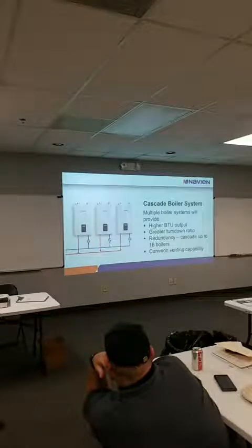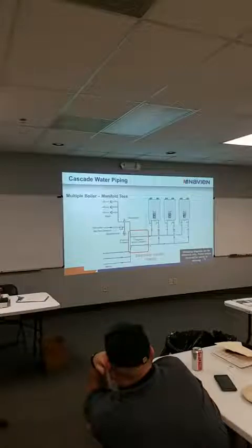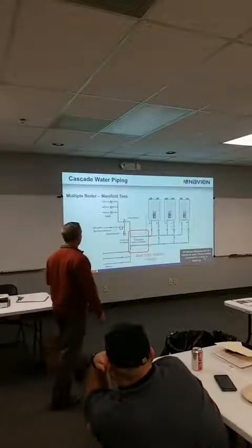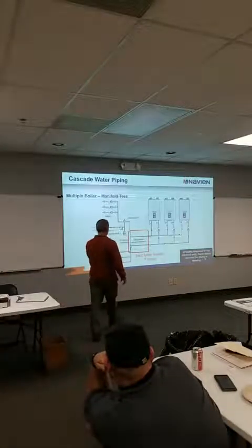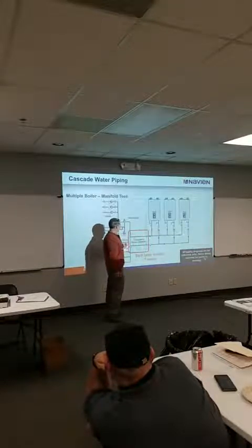So again, nothing special here. We can put up to 16 boilers together. We can common vent up to 8 of these in a system. All the drawings look the same. These boilers do come with one temperature sensor, so you don't need to buy these. You can just use one out of the other box.